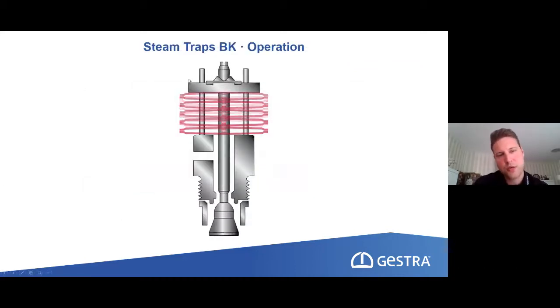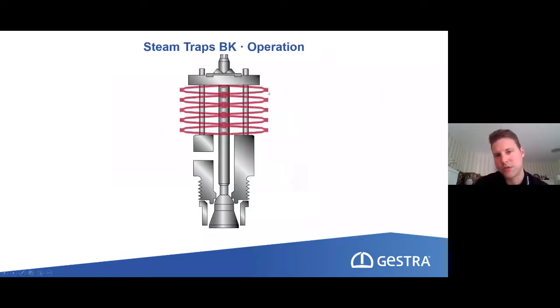So now you see the working principle. We have the stacked bimetallic plates that we see here, and this leads to the lift of the control unit. Here you can see that it is tight, so we have high temperature, close to saturation temperature. Now the condensate needs to cool down by around 20 Kelvin before these bimetallic plates become weak again, so that the bending is not there anymore, and it will open the orifice and discharge the condensate.